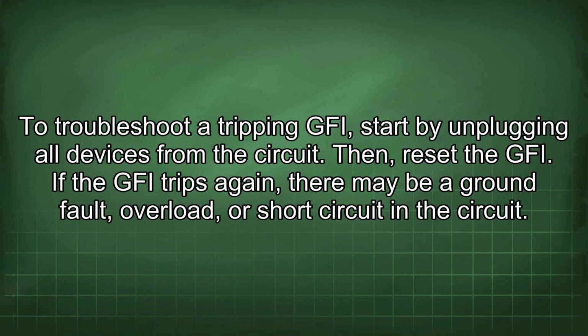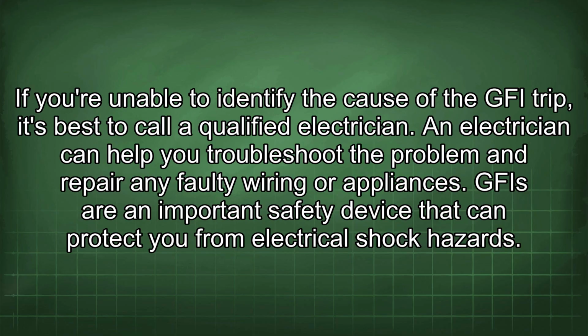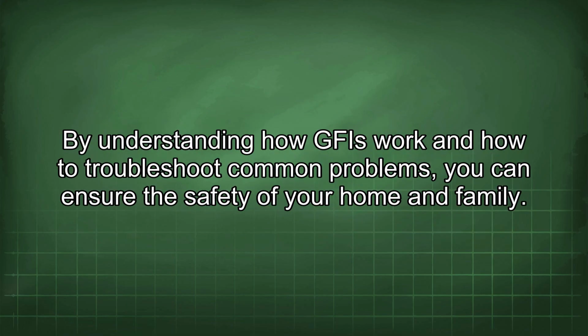To troubleshoot a tripping GFI, start by unplugging all devices from the circuit. Then reset the GFI. If the GFI trips again, there may be a ground fault, overload, or short circuit in the circuit. If you're unable to identify the cause of the GFI trip, it's best to call a qualified electrician. An electrician can help you troubleshoot the problem and repair any faulty wiring or appliances. GFI are an important safety device that can protect you from electrical shock hazards. By understanding how GFI work and how to troubleshoot common problems, you can ensure the safety of your home and family.